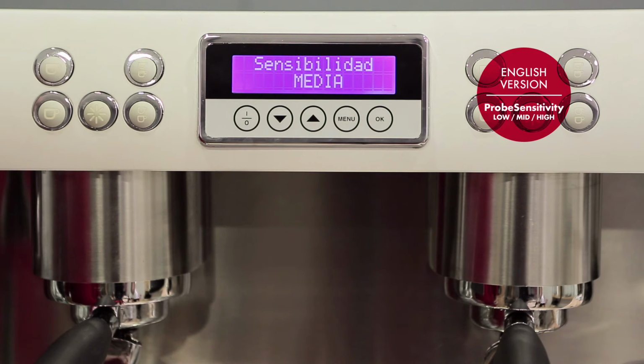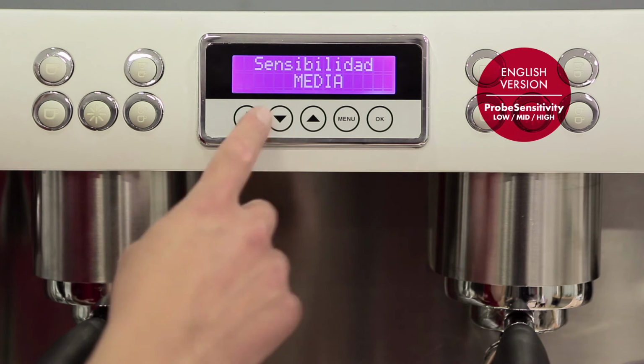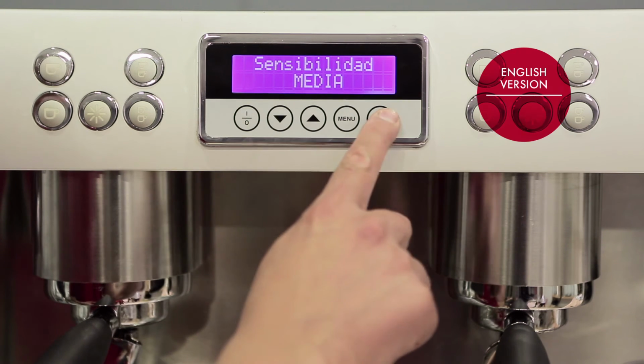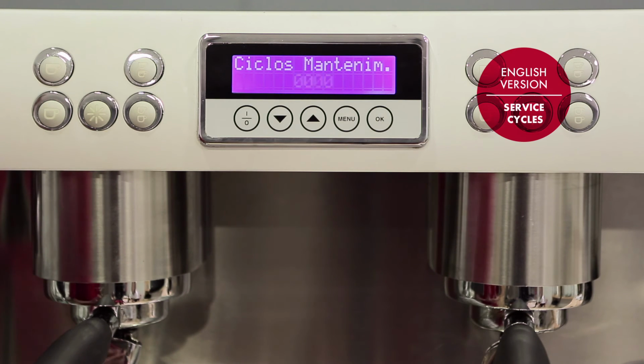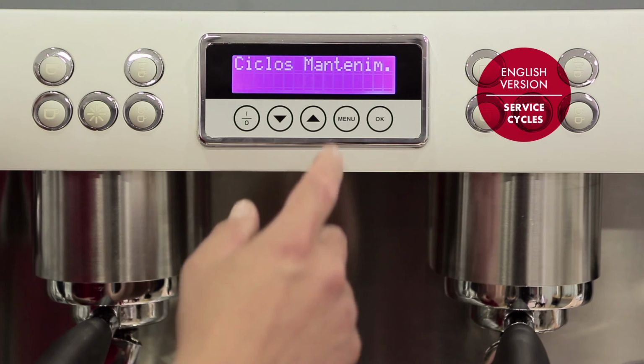The next option in the menu is the sensitivity option. This function allows us to vary the sensitivity of the level probe of the boiler in three positions: low, medium, or high. Our recommendation is to select medium sensitivity and only if working with highly purified water to use high sensitivity. The following function of the menu is the maintenance schedule. It tells us the number of services for which the machine will flash up a visual warning on the display to perform some kind of maintenance. To disable this function, it's sufficient to set it to zero.